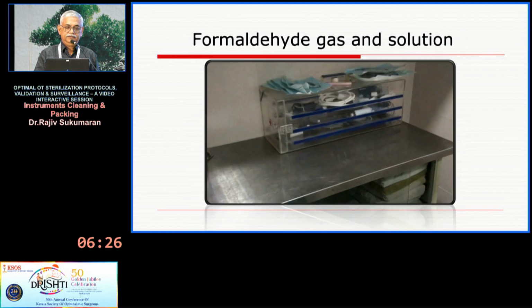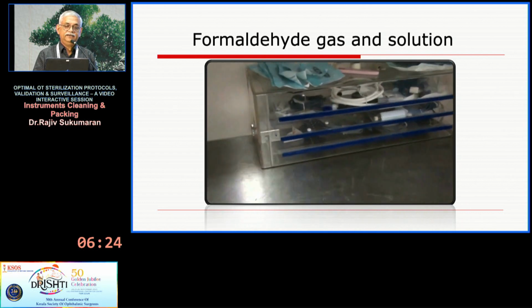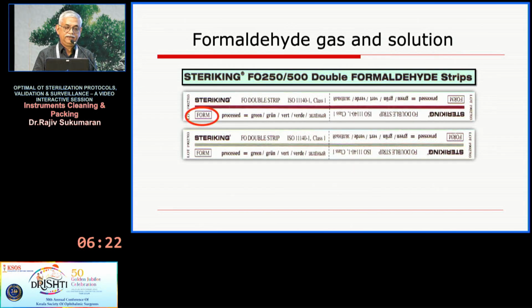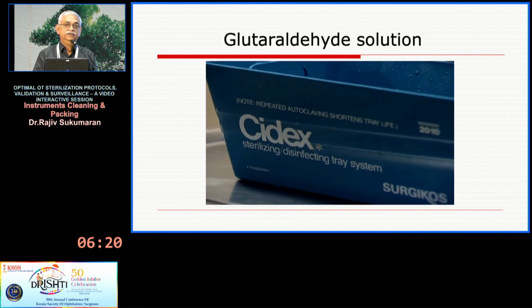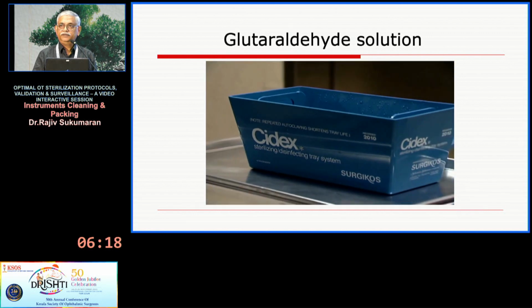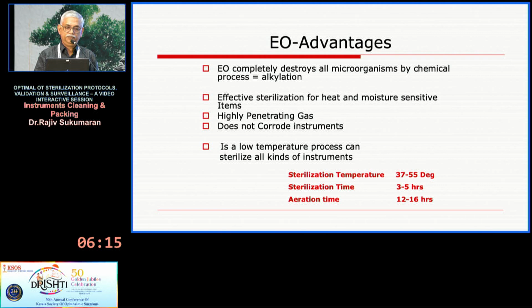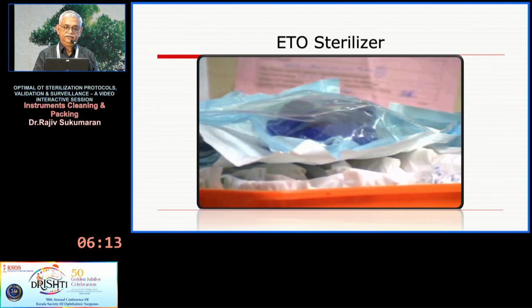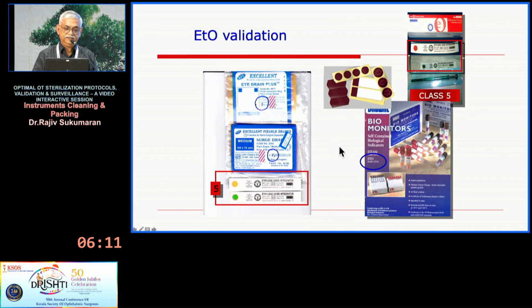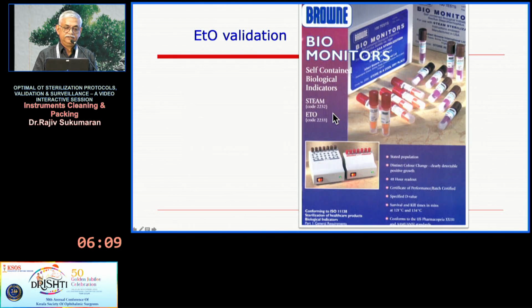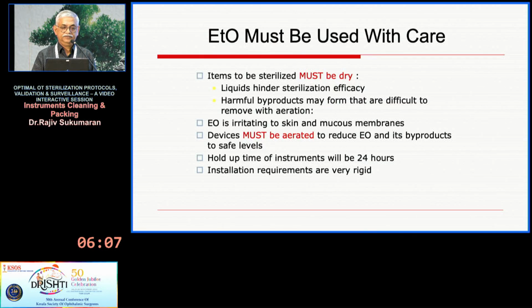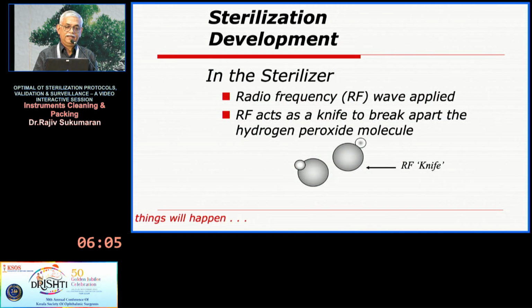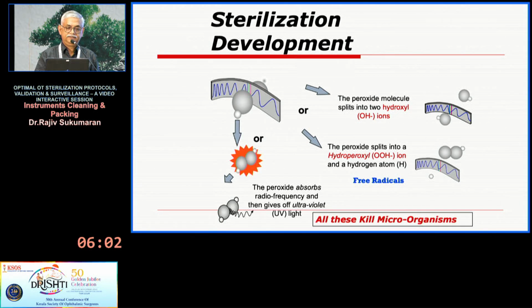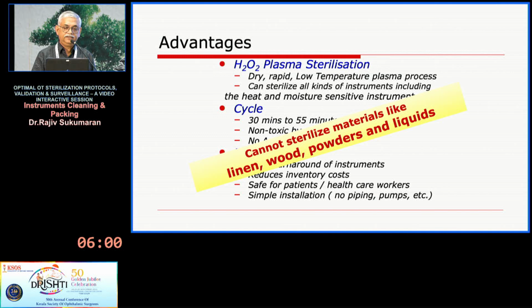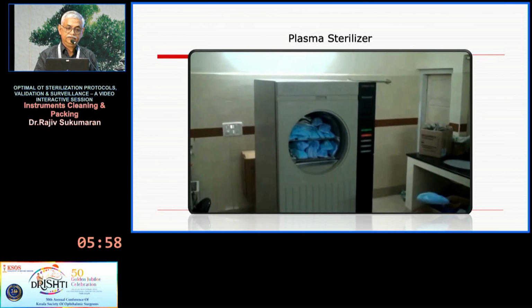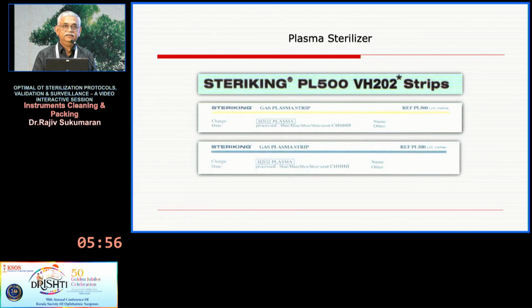And steam and formaldehyde should not be used in ophthalmic practice. There are indicators for it. Definitely Cidex should not be used for ophthalmic use. For ETO we have different sterilization indicators. One is the biological, which I had shown already. For plasma sterilization, there again the biological indicators can be used. This is the plasma, and these are the indicators for it.